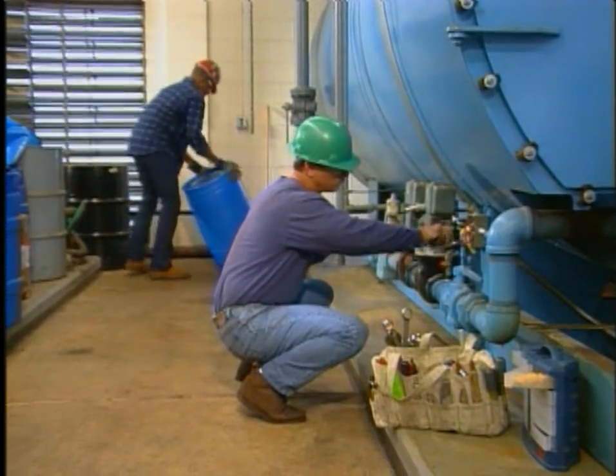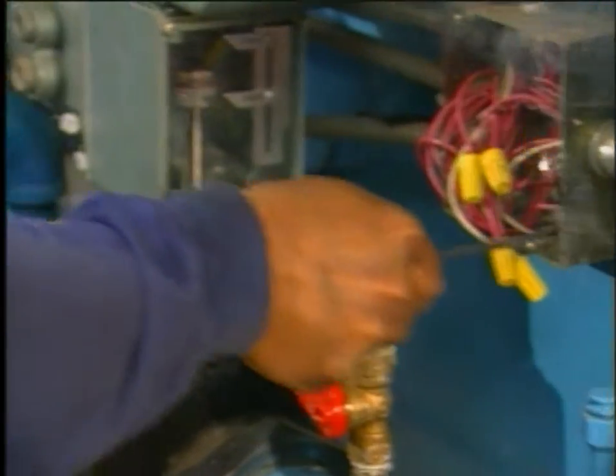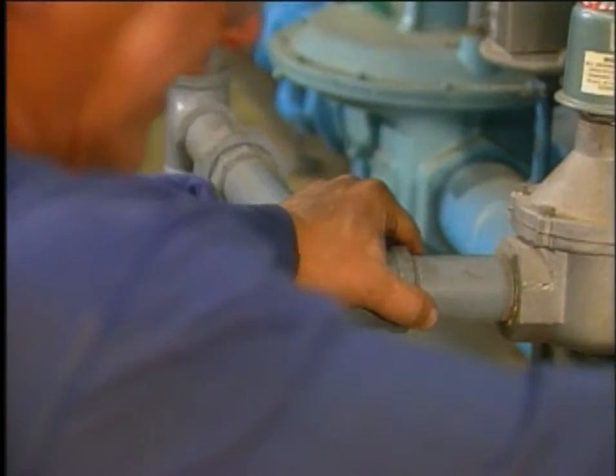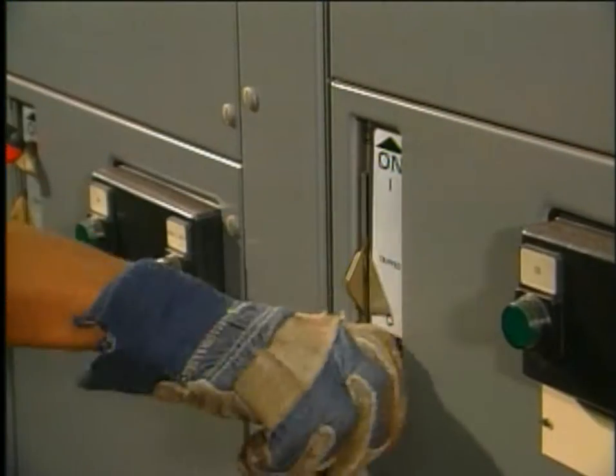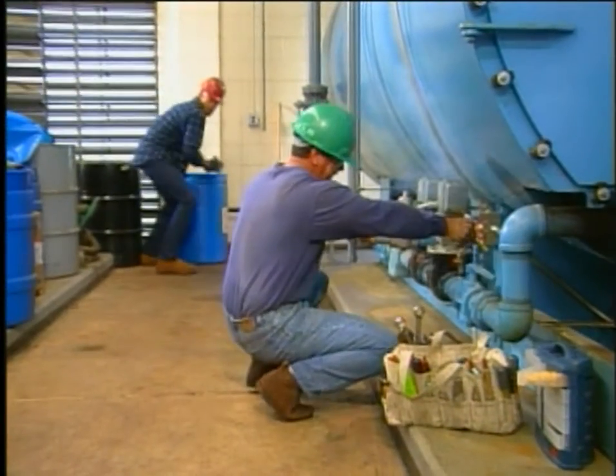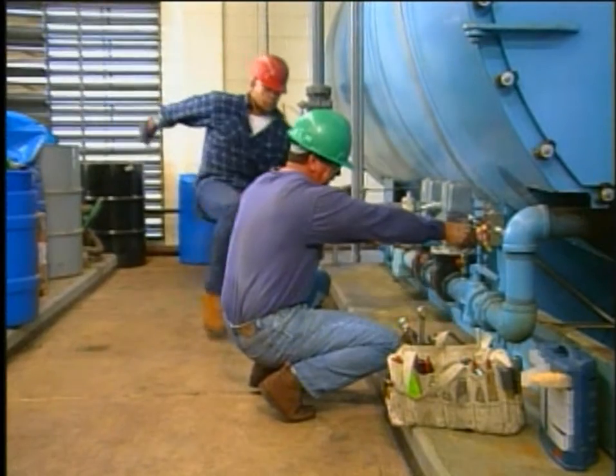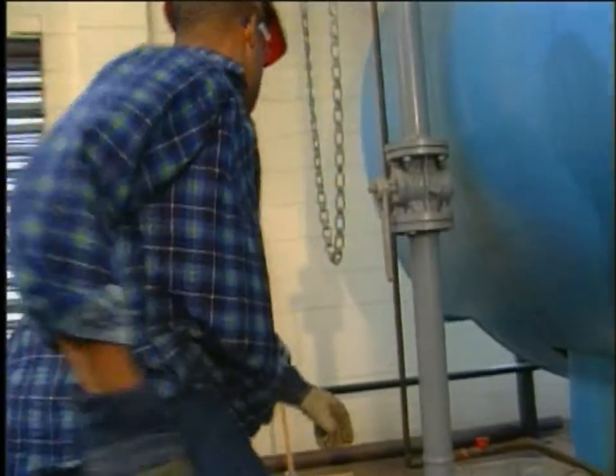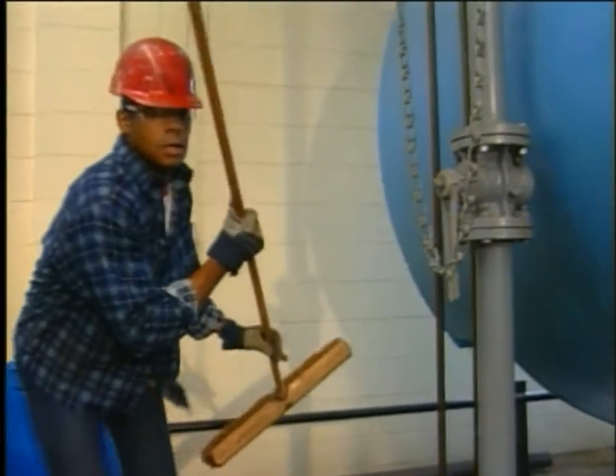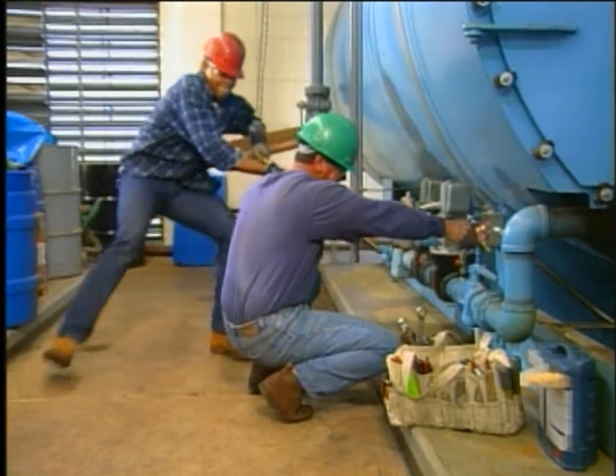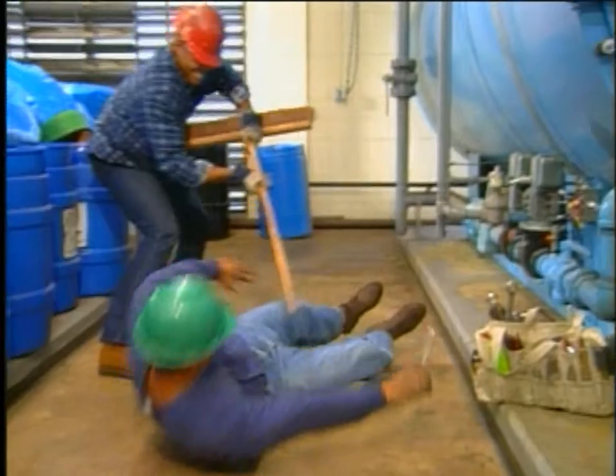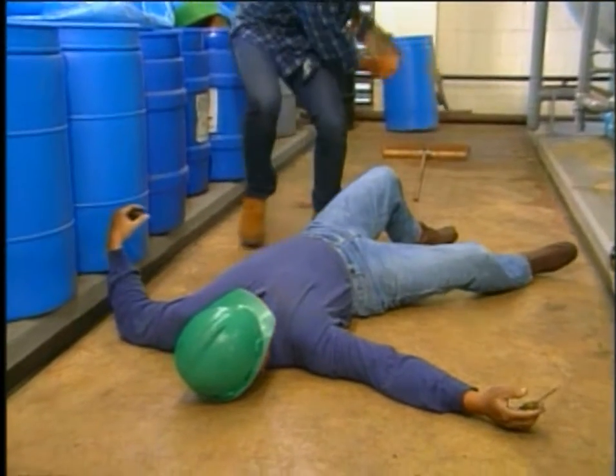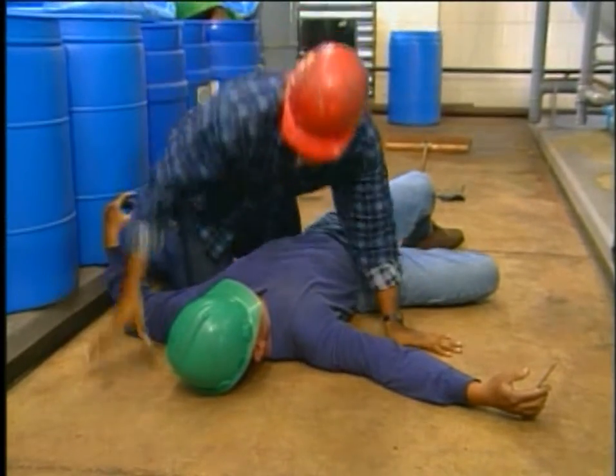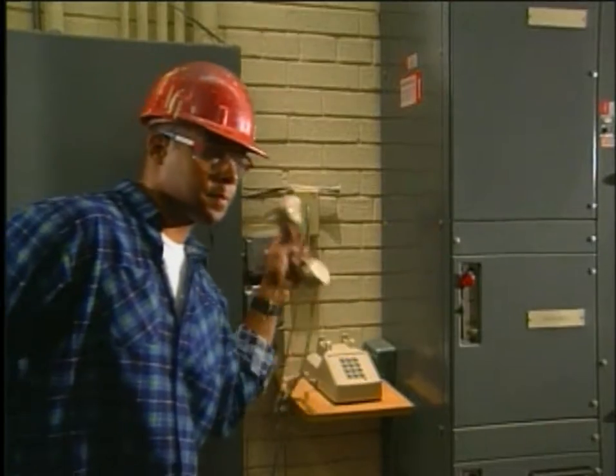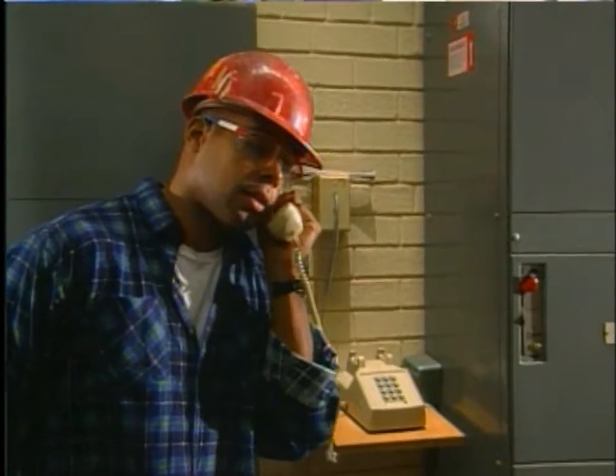Accidents can happen, and you need to know what to do to protect yourself and how to aid a shock victim. If you don't want to become a victim yourself, find out if the person you're helping is in contact with an energized circuit and shut it down before you approach. If you're not sure, assume that touching the victim could shock you. First, make every attempt to turn off the electricity. If you have to move someone off a live circuit, use something non-conductive, like a dry wooden chair, board, pole, plastic pipe, or rope. Be careful using wood exposed to humidity. Humidity fills wood with water, making it conductive. Once you have safely separated the victim from the energized circuit, call or send for emergency medical help.